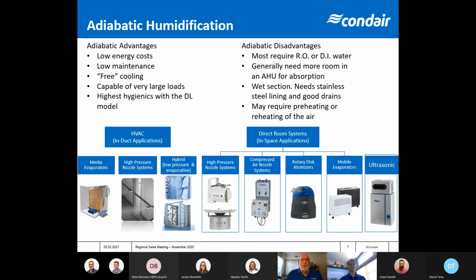The next one to the right is our high pressure nozzle system. We provide a high pressure pump supplied with RO or DI water sprayed into the air. With this system here, we can do really large loads, up to over 3,600 pounds per hour out of a single unit. We really kind of look for a minimum of about 100 pounds. With this system here, these have very, very good tight tolerances. So we can turn these all the way down.